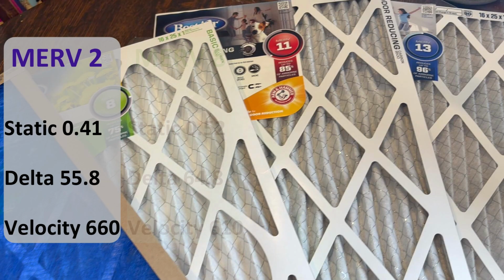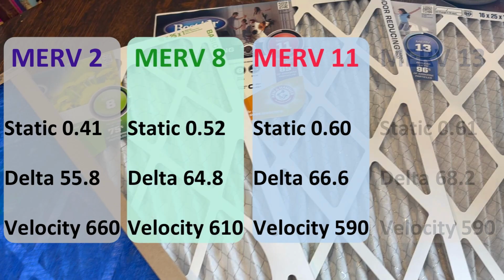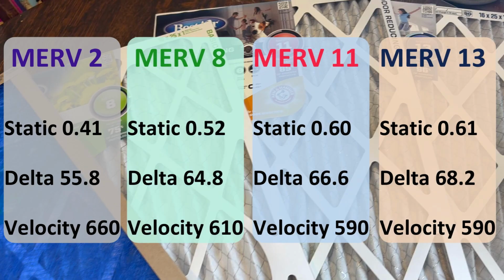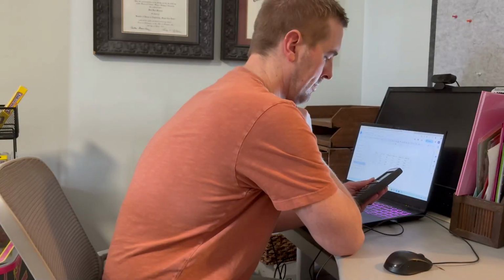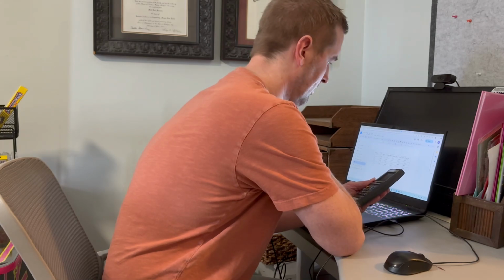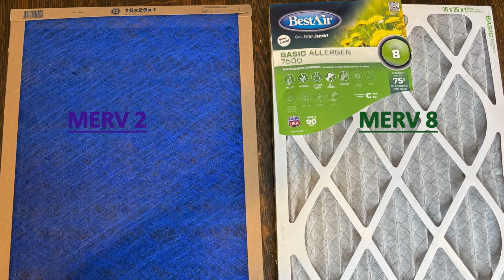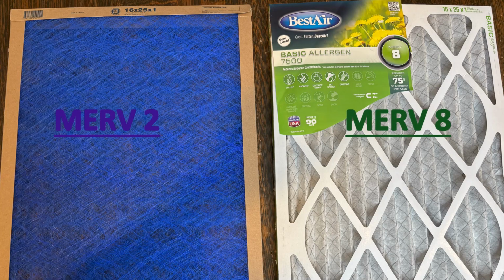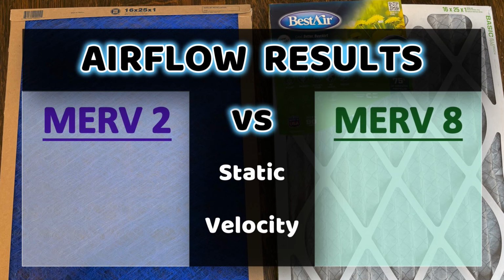Now that we have the data, we can go ahead and start our comparison of the 4 filters against each other. And after spending tedious amounts of time analyzing the data, I'm just kidding, data was really evident. Unsurprisingly, the MERV 2 provided the best airflow, least amount of static. But even though the MERV 2 did have the best airflow, it's still worthwhile to do a comparison to see this fiberglass MERV 2 versus our pleated MERV 8. Let's just see how much of a difference we had.